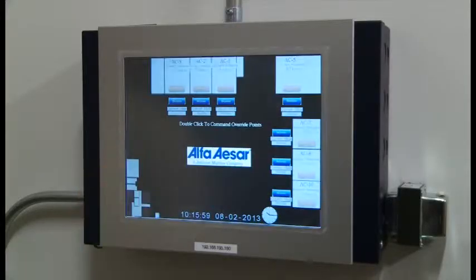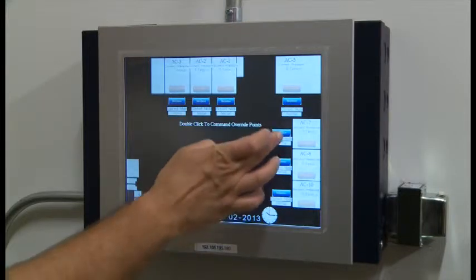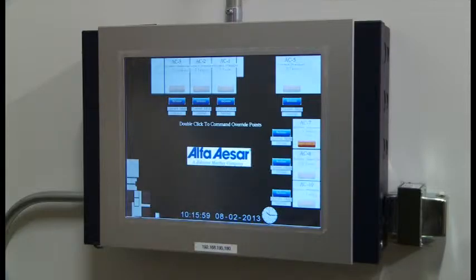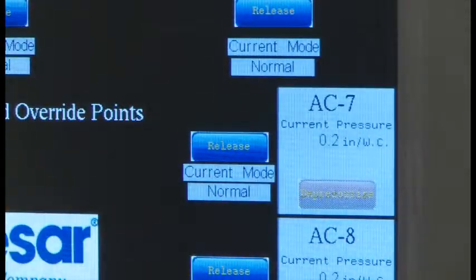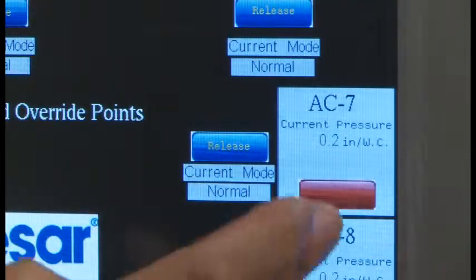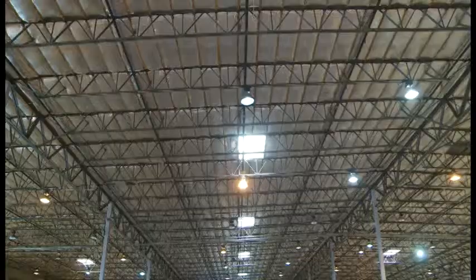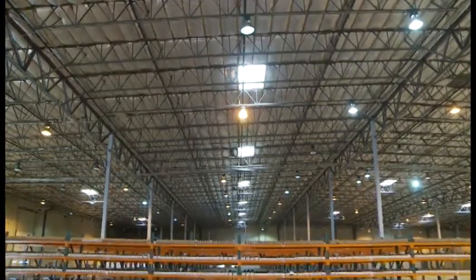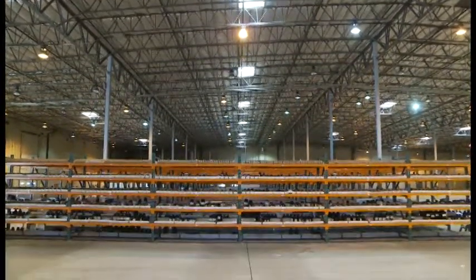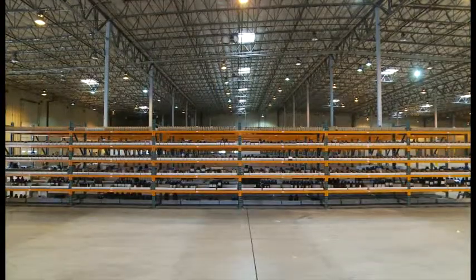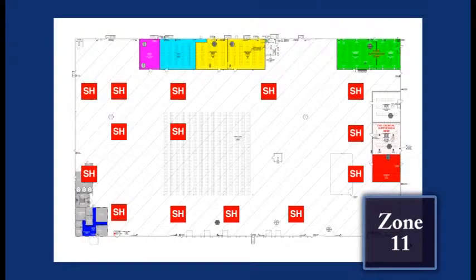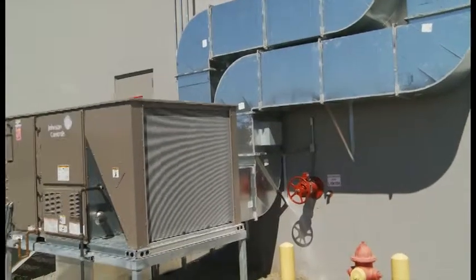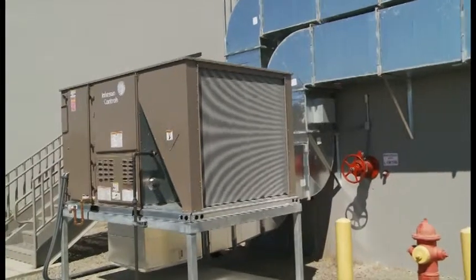Controls for the manual operation of the air handling units are located next to the fire alarm control panel in the fire alarm control room and in the AFFF-AR tank room. These provide the ability to pressurize various adjacent portions of the building in a controlled manner to mitigate the accumulation of smoke or noxious odors so that emergency response personnel may more effectively enter the building. The areas identified as Zone 11 have 14 smoke vents that can be manually opened to release smoke at those locations. The air handling units for each area have 3 modes of operation.